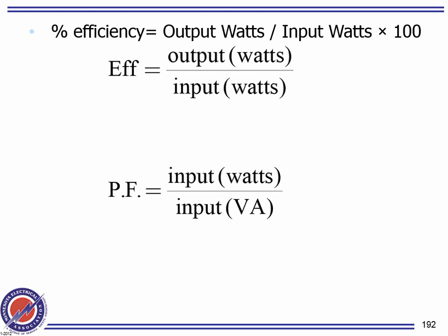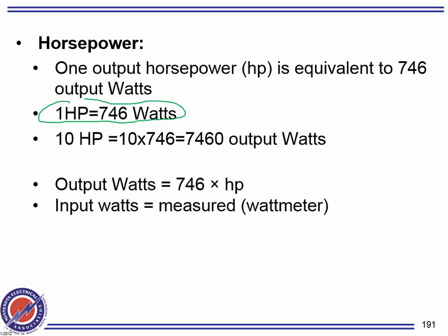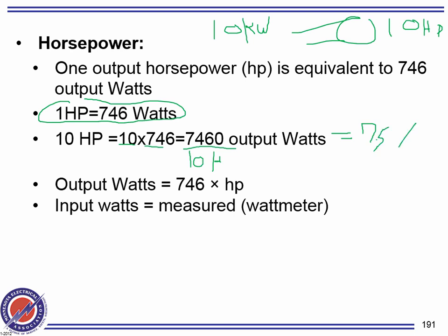Efficiency of the equipment, meaning how much power you can get. So let's just take this one here, for example. Suppose this machine is my machine. It's a 10 horsepower machine, and I'm bringing 10 kW to a 10 horsepower machine. What's the efficiency of that machine? Piece of cake. You have to convert the horsepower into kW and divide this by 10 kW. Remember, here's my horsepower times 746, divided by 10,000. And anybody can see that this is actually almost 75%. This machine is only a 75% efficient machine, right?